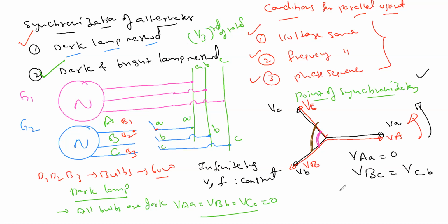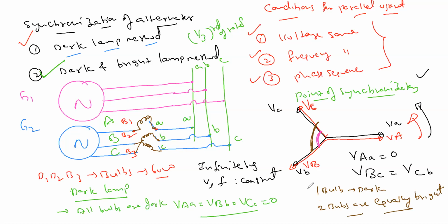If it is not the point of synchronization, same voltage means equal brightness. So in the dark and bright lamp method, one lamp is connected here, another lamp between here, and another lamp between here. So one bulb is dark, and two bulbs are equally bright, simultaneously. One bulb should be dark, and two bulbs simultaneously bright with equal brightness, not one brighter and the other dimmer.